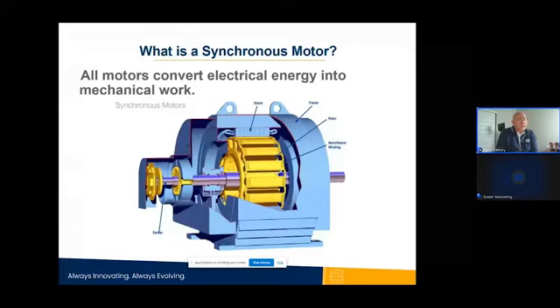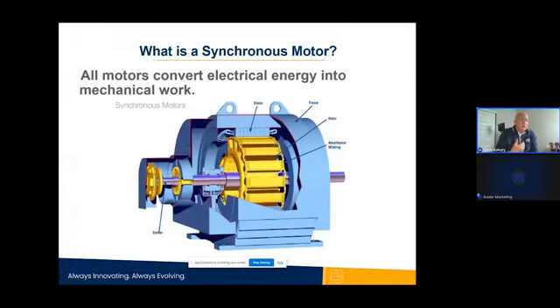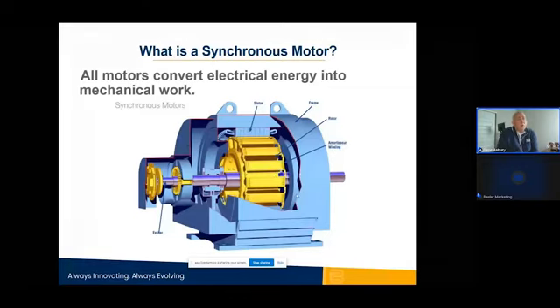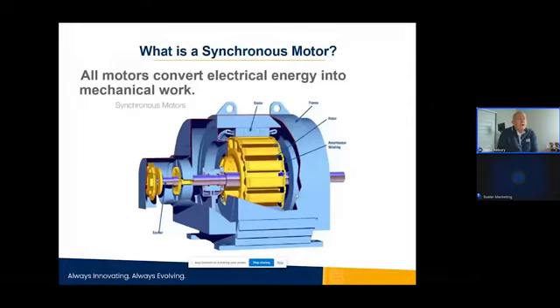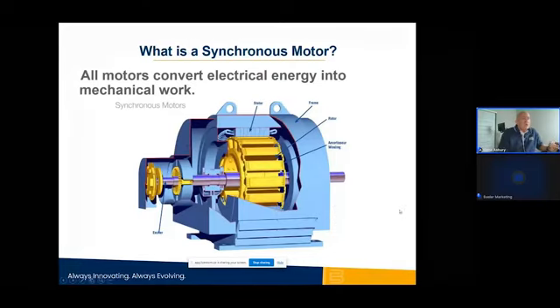And just like in induction motors, this is the winding that really causes the interactions between the RMF of the stator. When power is supplied to an induction or synchronous motor, there's an RMF that's developed that's at the frequency of the power being supplied. So you need something to start the motor. So the interaction between this amortisseur winding and the RMF that's generated will start that rotation of the motor.